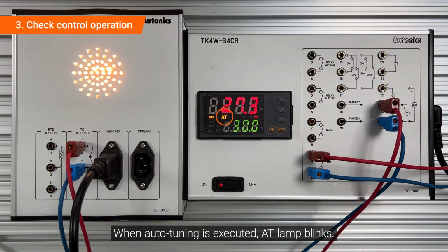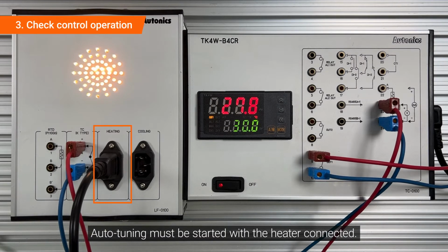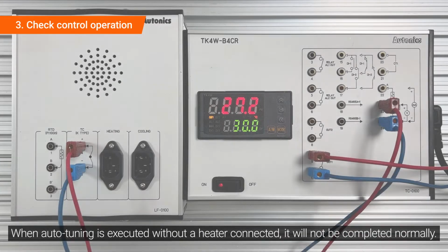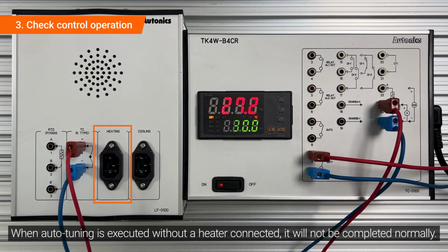When auto-tuning is executed, the AT lamp blinks. Auto-tuning must be started with the heater connected. When auto-tuning is executed without a heater connected, it will not be completed normally.